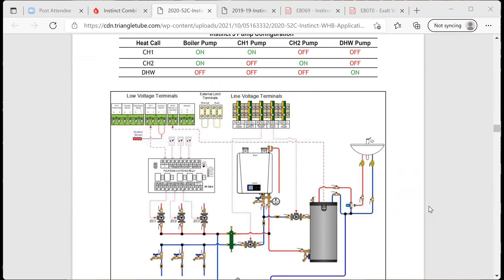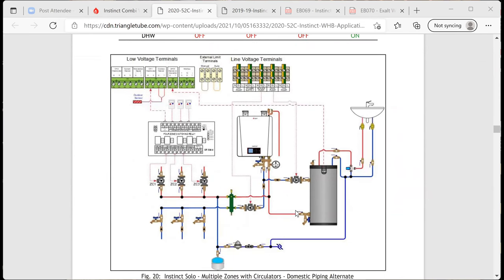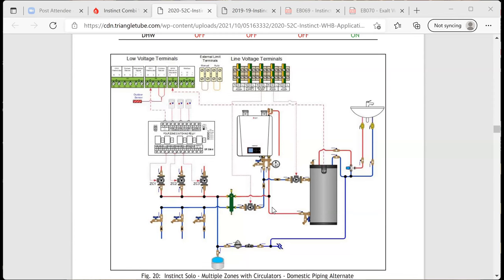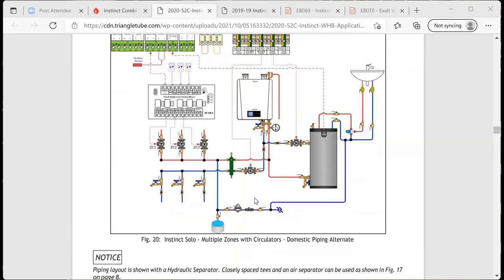Let's take a look. Okay, so this is an indirect. All right, so this is the indirect off the primary side. See some issues with this in the field quite a bit on the piping. The one thing with this, it shows check valves right here. I don't think in our day and age we need these anymore because pretty much every pump out there has an internal check.